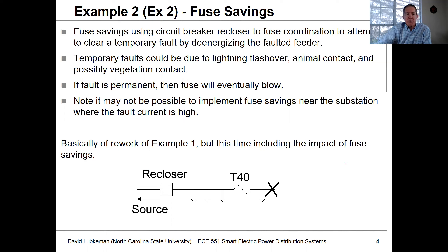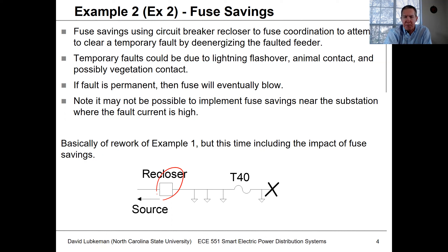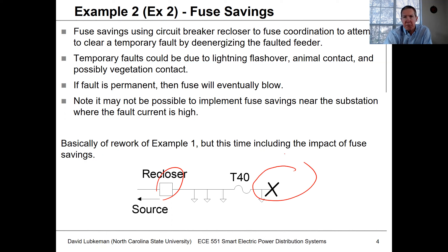This could be due to lightning, temporary animal contact, or temporary tree contact if wind blows trees into the wires. What Mr. Guida talked about was a situation where you have an upstream reclosing device — this could be a line recloser or a station circuit breaker — with a protected section downstream protected by a fuse.